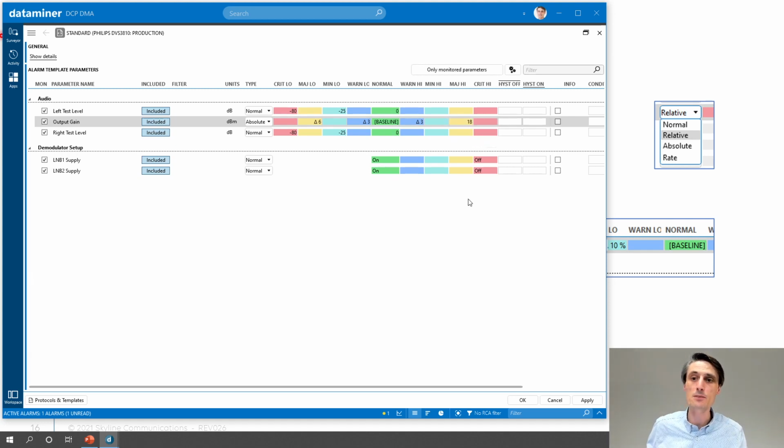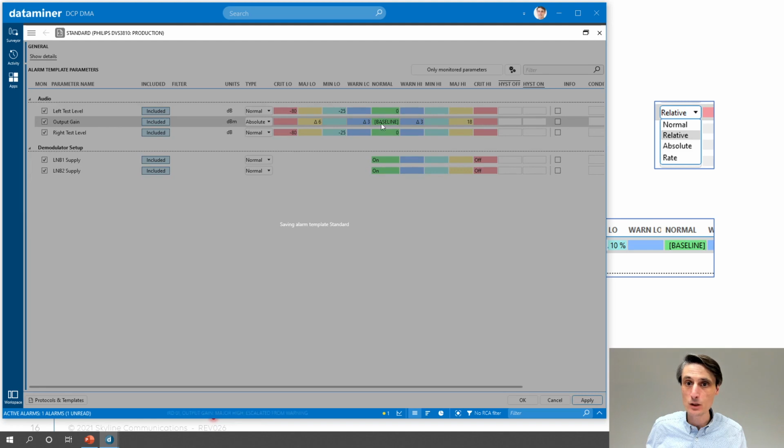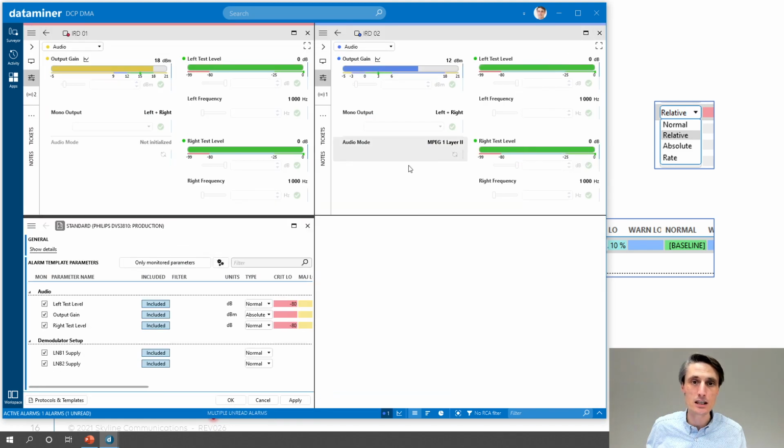If I enable that checkbox fixed, it will say that at any time, doesn't matter what the baseline is, 18 is a major high. So now it doesn't matter that my normal value is 15 and this should be warning. I actually say 18 at all times is my cap there. That's a fixed threshold. So in this case, it's also here now fixed on 18.